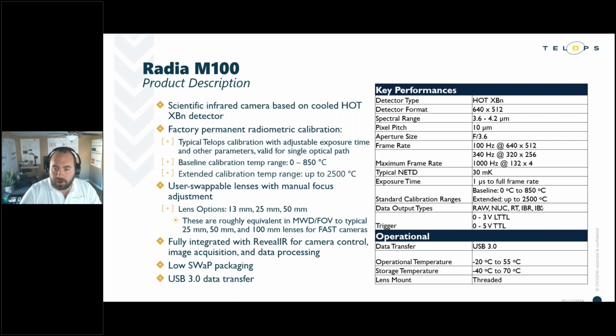Like I said a little bit earlier, the baseline temp range on our calibration goes from 0 to 850 without the need for any neutral density filters. This can be extended out to 2500 C with the addition of a single attenuating filter.